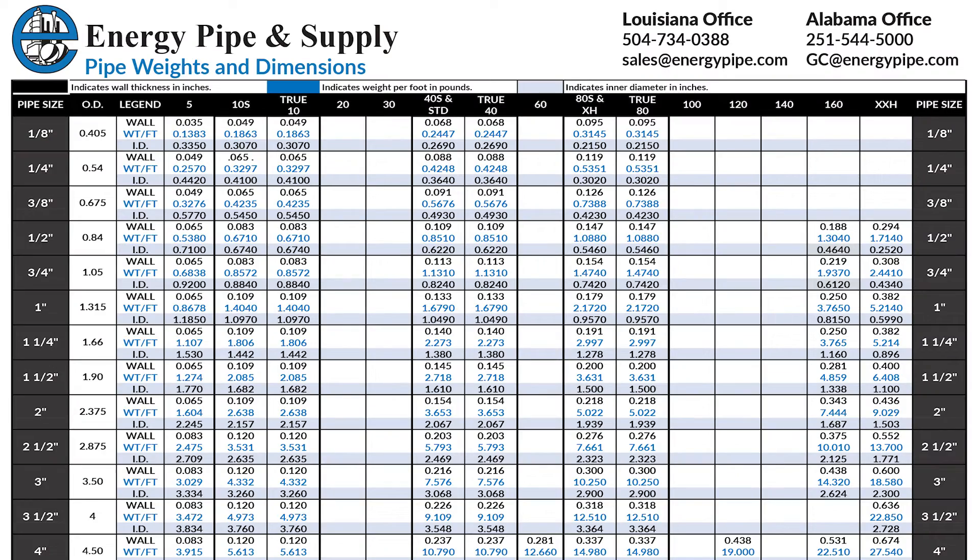If you go out and measure the size of pipe and you look at 3 inch pipe, the outside diameter from one side to the other is going to be three and a half inches. But they were looking for that ID to be three inch. So when you're trying to put together your sizing for pipe, you can look at a general pipe chart and it's going to show you the OD.